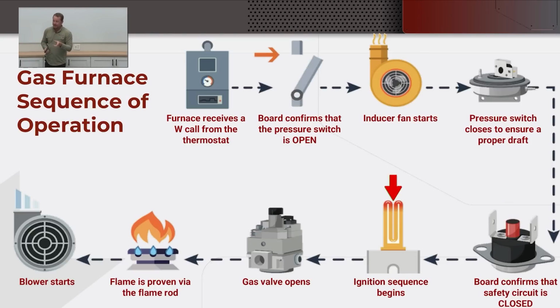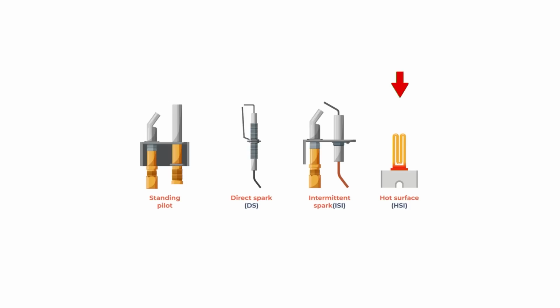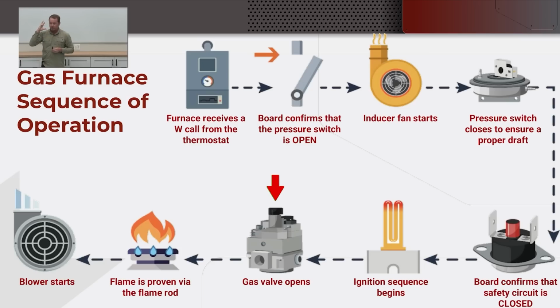Ignition sequence begins. This is just showing a hot surface igniter, but it could just as easily be spark ignition. And so that thing's going to glow. It's going to heat up. Then the gas valve opens, and that's on a timer. That timer in modern furnaces and gas appliances usually is flexible, meaning that the board is actually looking at how long it had to heat up last time, and it keeps shortening the time a little bit until it doesn't work, and then it goes to that last timing.